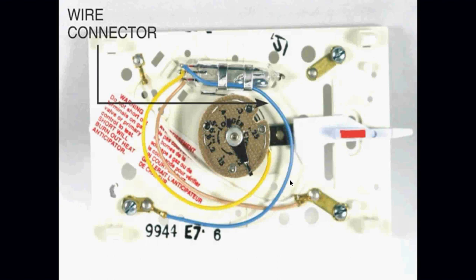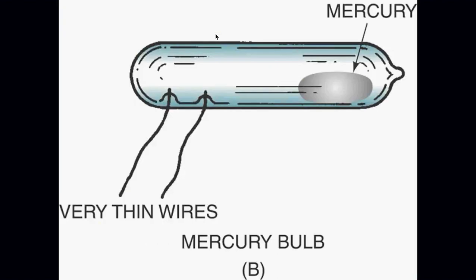Okay, again, the mercury ones, they're starting to go out, but they're still important. They're still out here on the market, okay? And they even give you a spot on all of these across the top. There's one right there and one right there. You can stick a level across it to make sure they're level. The biggest issue that I see when people install these old-style thermostats, and I hope they're not installing them anymore, but I've seen, is they're not level. If they're not level, you're not going to maintain proper temperature. Okay? Very important. And again, the mercury goes back and forth. It's connected to thin wires that go through the glass housing. And based on where the mercury is, it's either heat on or cool on or nothing at all.